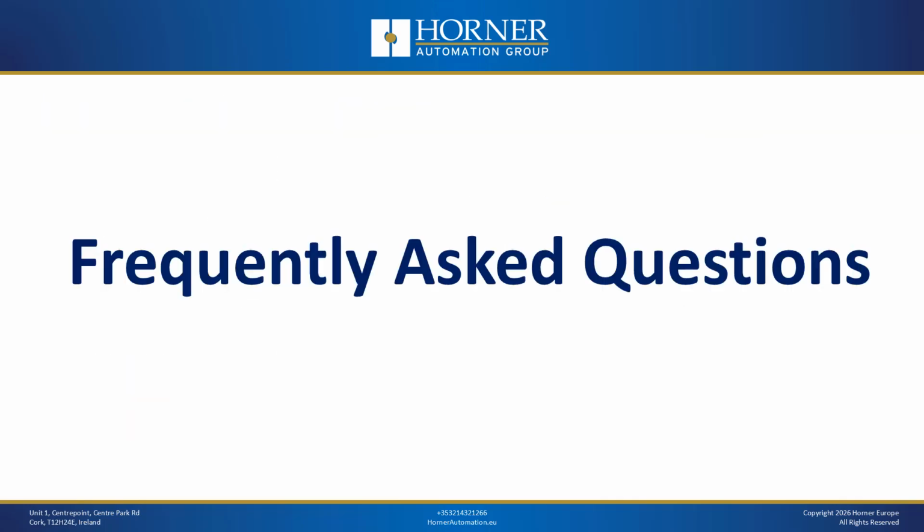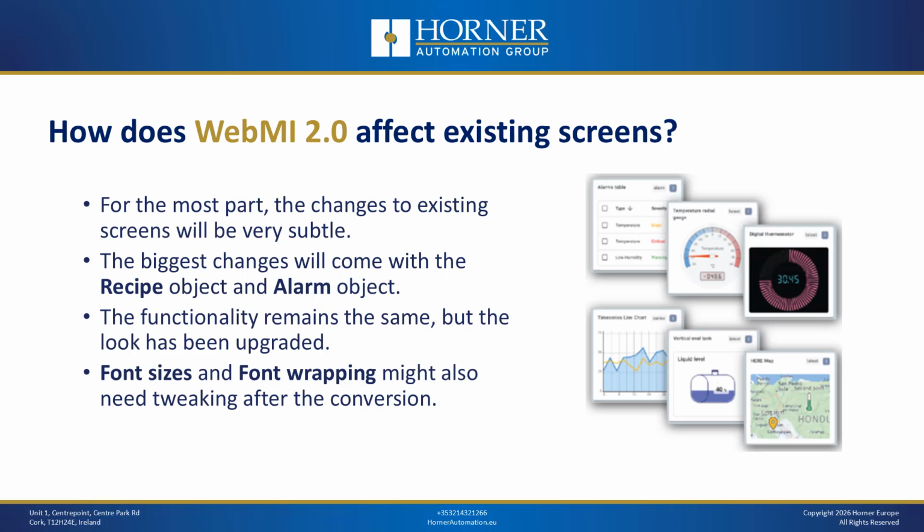Now, we are going to answer some frequently asked questions about the WebMI 2.0 transition. How does WebMI 2.0 affect existing screens? For the most part, the changes to existing screens will be very subtle. The biggest changes will come with the recipe object and alarm object. The functionality remains the same, but the look has been upgraded. You may need to do some slight tweaking to the text or images used, but your program's functionality will remain the same. Generally speaking, for all objects, font sizes and font wrapping might also need some tweaking after the conversion.